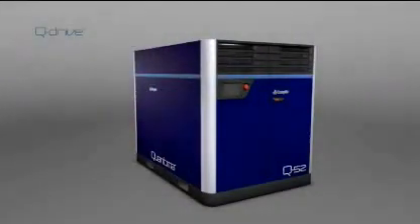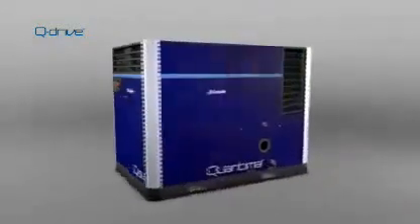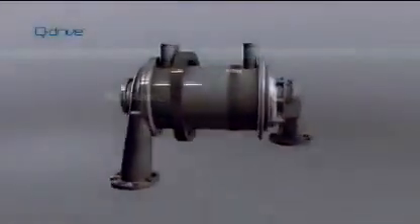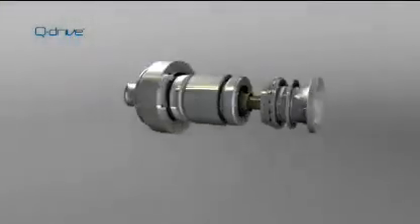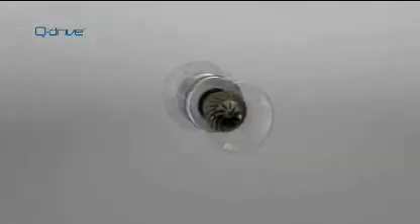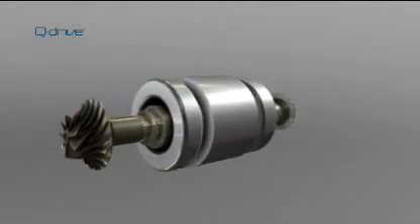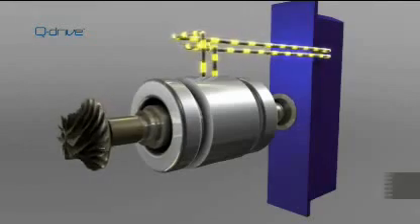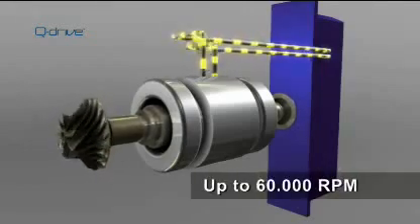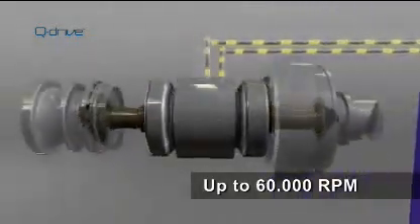The main philosophy of the new technology is to abandon the gearbox to drive the compressor. The core of QUANTIMA is Q-Drive, a high-speed induction motor with electromagnetic bearings. Both rotor shaft ends have a directly coupled impeller, giving a very compact two-stage design, meaning that QUANTIMA is approximately half the weight and half the physical size of an equivalent screw compressor. When the unit is powered, the rotor starts to levitate and begins to rotate, driven by the inverter all the way up to the design speed of the impellers.